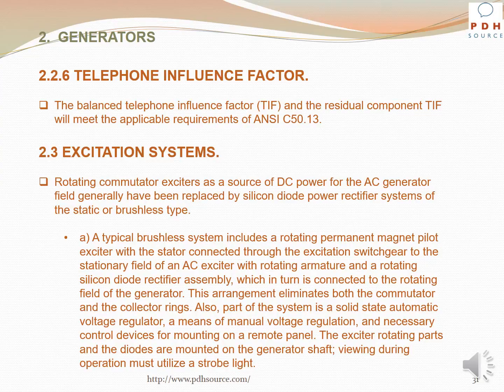Also part of the system is a solid-state automatic voltage regulator, a means of manual voltage regulation, and necessary control devices for mounting on a remote panel. The exciter rotating parts and the diodes are mounted on the generator shaft. Viewing during operation must utilize a strobe light.